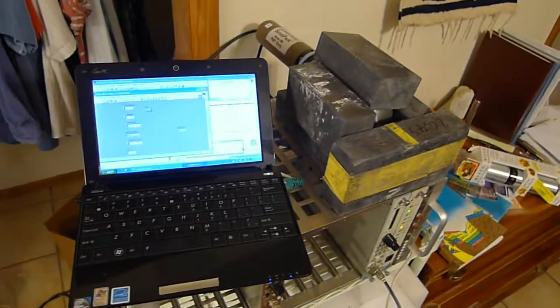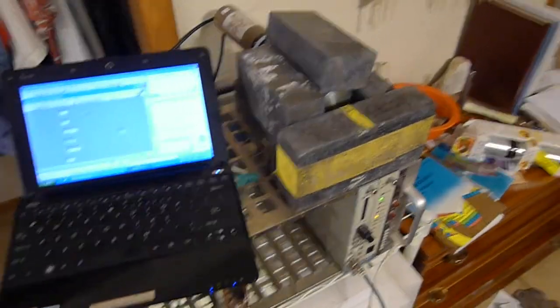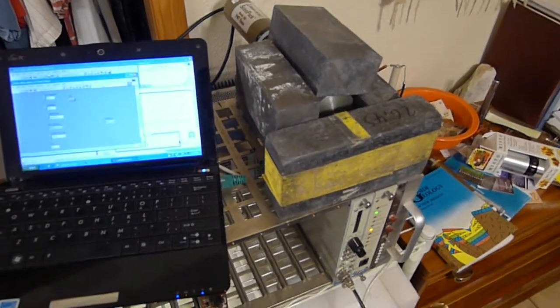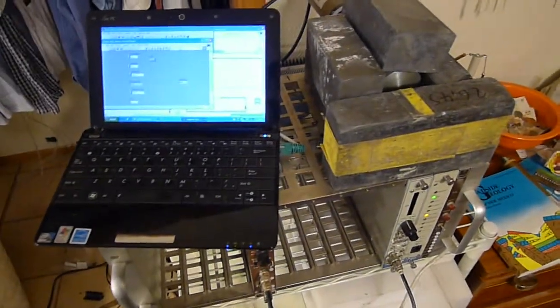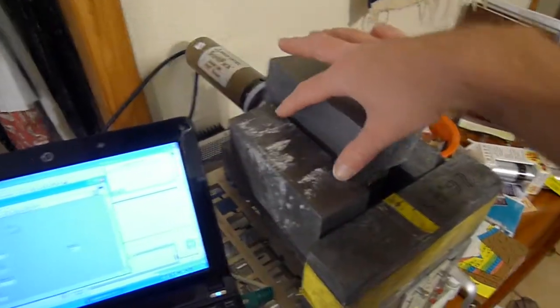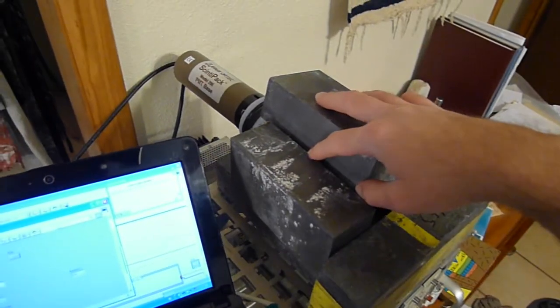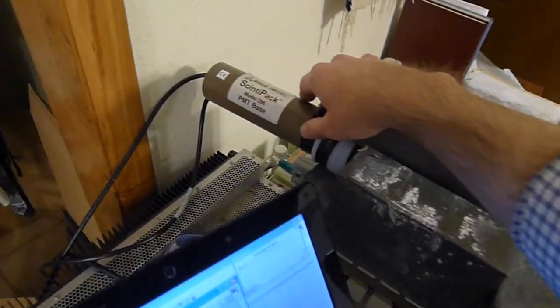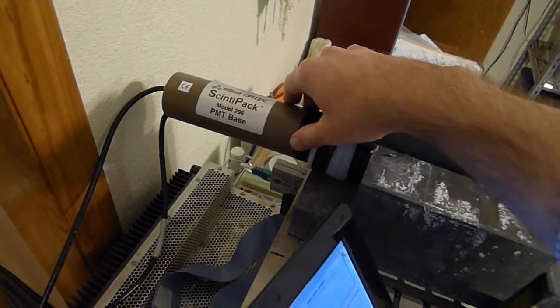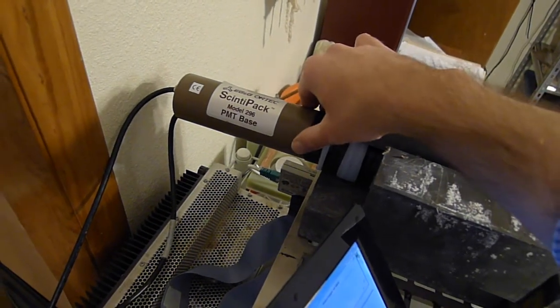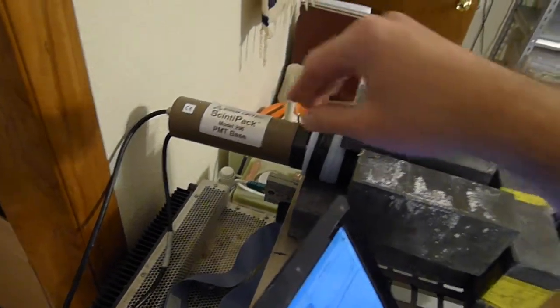However, I think it has some notable differences, and I'll just discuss my approach to doing the same thing in essence. First of all, this is a means of detecting gamma rays. So there's a 2x2 inch sodium iodide detector here. It's got a base that contains the power supply at 900 volts and a charge sensitive preamplifier.